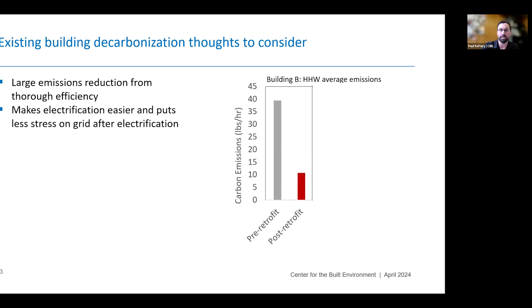On today's current grid, if you were to partially or fully electrify those loads using an air source heat pump, you would definitely get additional emissions reductions. But partial electrification would actually reduce emissions by almost the same amount as full electrification, at a fraction of the cost, embodied carbon, and refrigerant losses. And those heat pumps would operate at more uniform loads instead of potentially cycling, which happens when very large air source heat pumps are installed, as we've seen in several projects.